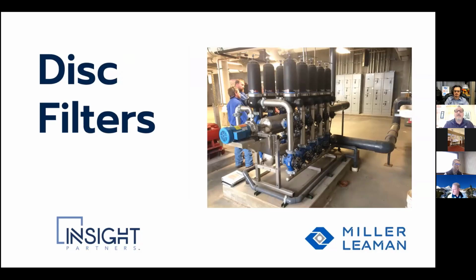Filtration was first invented by Boeing aircraft. They used it on the B-17s for hydraulic fluid, and it was incorporated in the 1960s for water use, to filter the water. It's a stack. I have an example downstairs, with different micron discs, a different stack of discs built up on each other, and then the water travels through a set of grooves on the disc, which crosshatch, so you don't get a least path of resistance. And then in turn, it'll filter the water and polish the water as it's traveling through the disc, sending it back to the sump or sweeper systems, whatever you may have on the cooling tower. And we're going to give you a demo of that going downstairs.